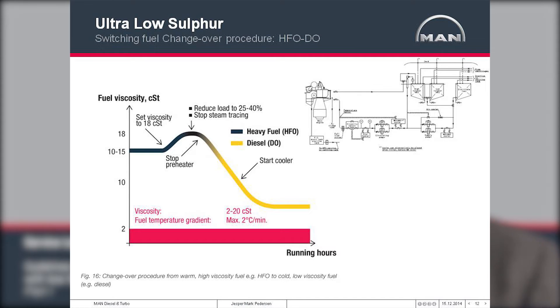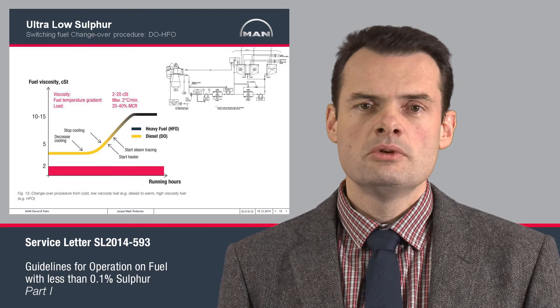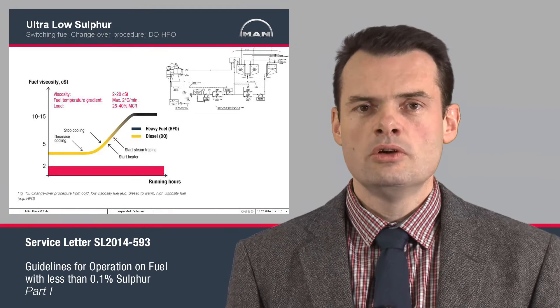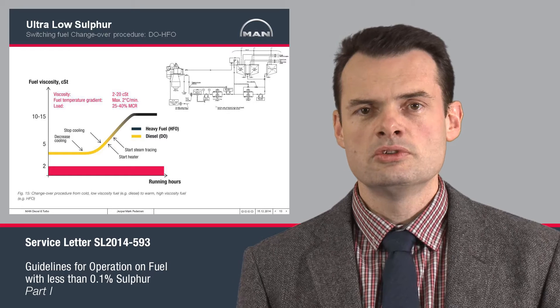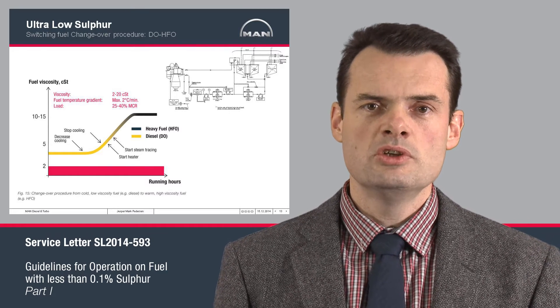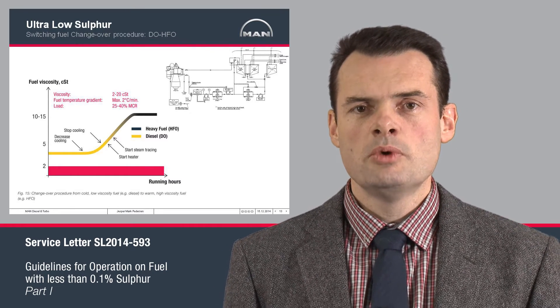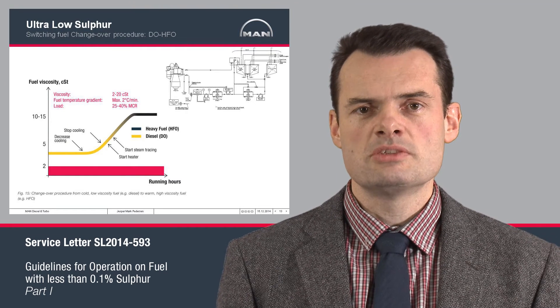When switching from a hot fuel to a cold fuel, the bound heat in the fuel system will impact the viscosity very quickly. It is therefore key to make sure that the amount of distillate fed into the system is not too high. When switching from a cold fuel to a hot fuel, or a low viscosity fuel to a high viscosity fuel such as HFO heavy fuel, it is more important to keep an eye on the temperature expansion.